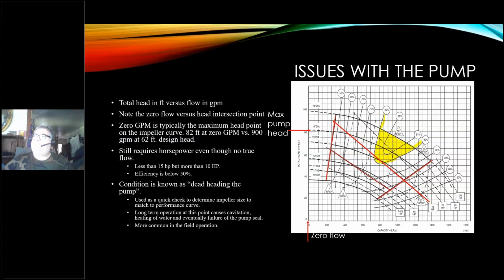Why is that? Well, the pump is a non-positive displacement device. In other words, it's going to pump right back into itself. If I've got nowhere for the water to go, it just bypasses right back into the suction inside the case. If you run like this for a long time, it will heat up. You'll actually heat the water up, and I've run into that also. This term is called deadheading the pump.